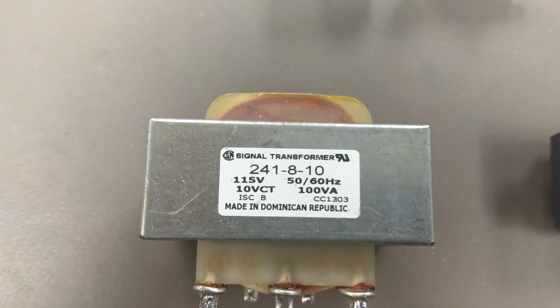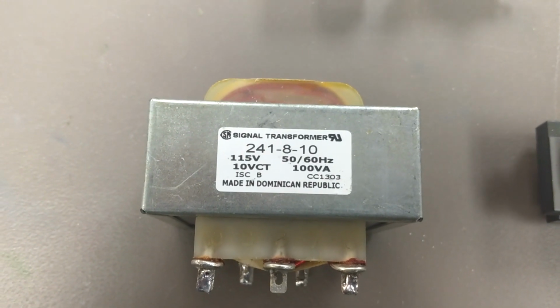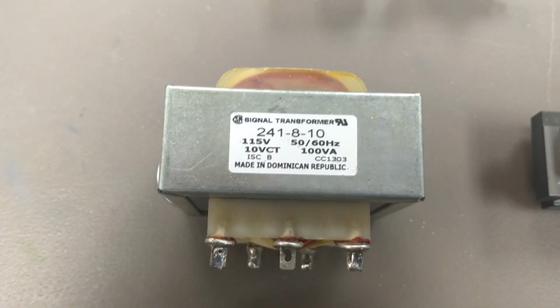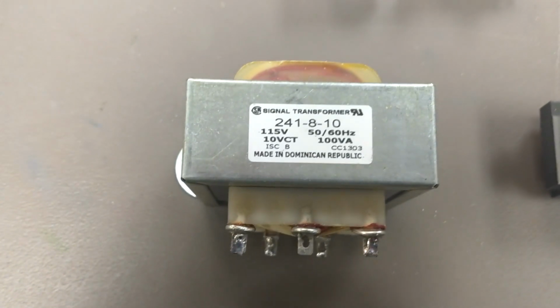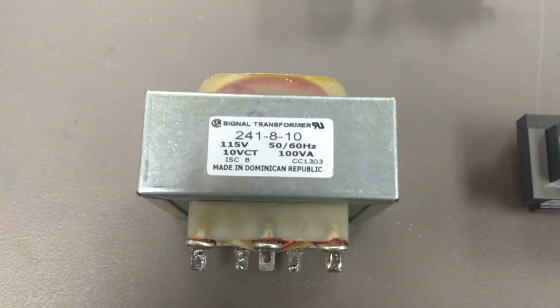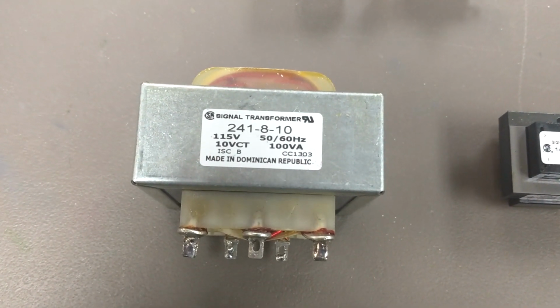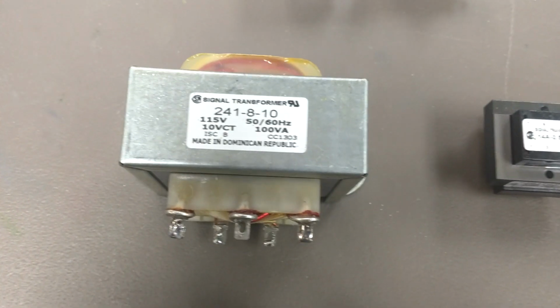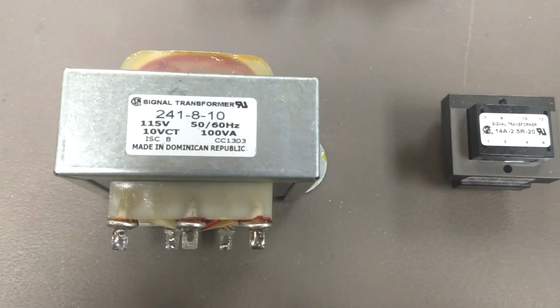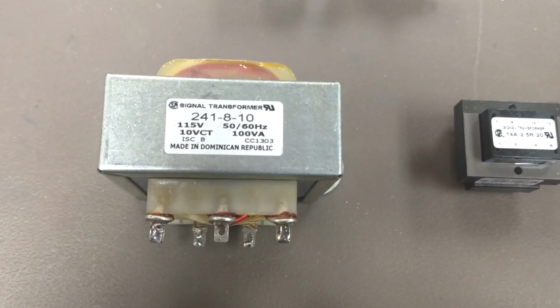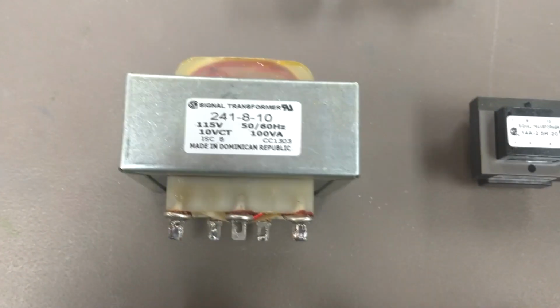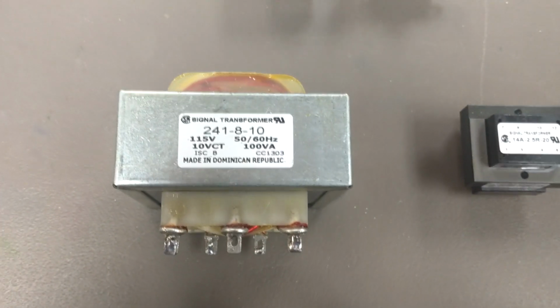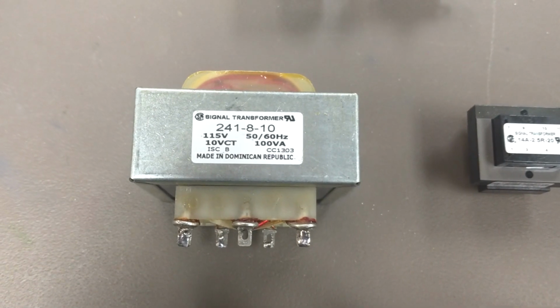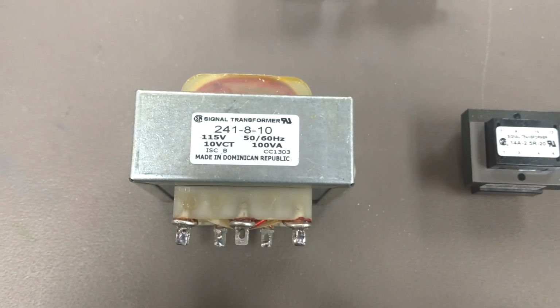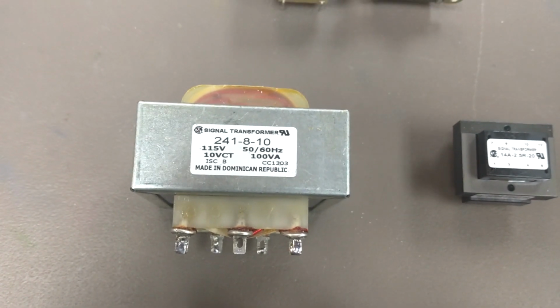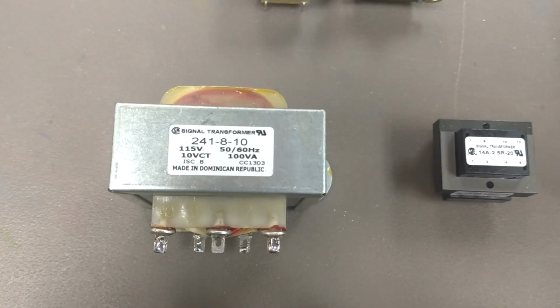This transformer is rated at 100 volt amps. The primary is 115 volts and the secondary is 10 volts. They're not rated in power, they're rated in volt amps. That's because I could power an inductor with this that would draw 10 amps, but that would be drawing no power, because the current would be at 90 degrees with respect to the voltage. So the transformer can supply 10 volts at 10 amps at any angle between the voltage and the current.